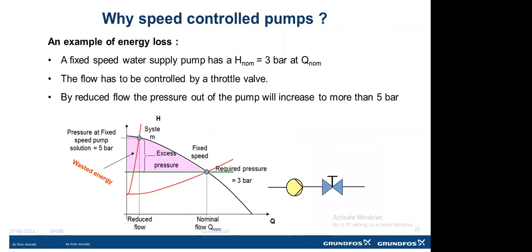A common practice for saving energy is speed control pumps for variable applications. Because how do we save the energy? Let's say, for example, we have designed one pump at Q nominal at 3 bar, and our flow requirement decreases, let's say due to variable flow. If we don't install the VFD, what happens in operation? We just throttle the valve, and we shift the duty point over the pump curve, the QH curve. Since we are creating artificial head, or we can say excess pressure, it requires energy to operate the pump at higher head.